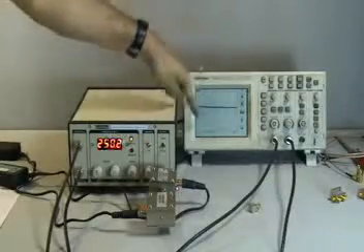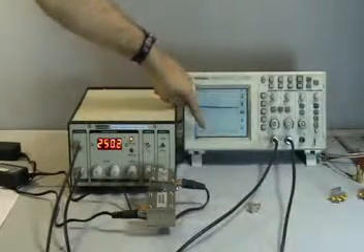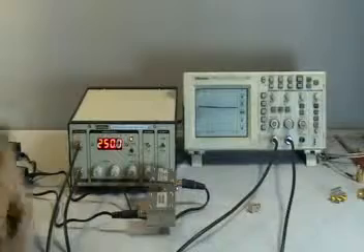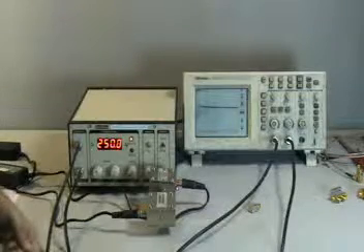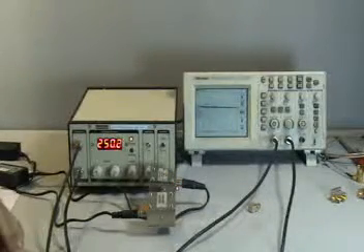We can decrease the calibration from 500 millivolts to say about 100 millivolts. That will bring the display to about 2 dB per division, and you may be able to measure the noise figure with slightly more precision.